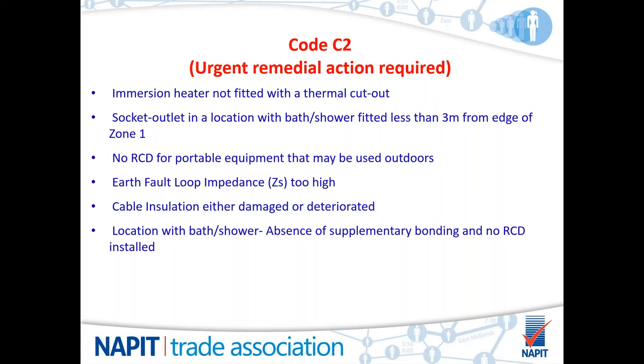No RCD for portable equipment that may be used outdoors. So again, if you were doing an EICR on, let's say, a block of flats, third floor flat, would the socket require RCD protection? Could that be used outdoors? So that would be down to your determination. A high earth fault loop impedance, or Zs. And cable insulation that has either been damaged or deteriorated, like we saw in the previous photographs, and a location with a bath or shower with the absence of supplementary bonding and no RCD installed.